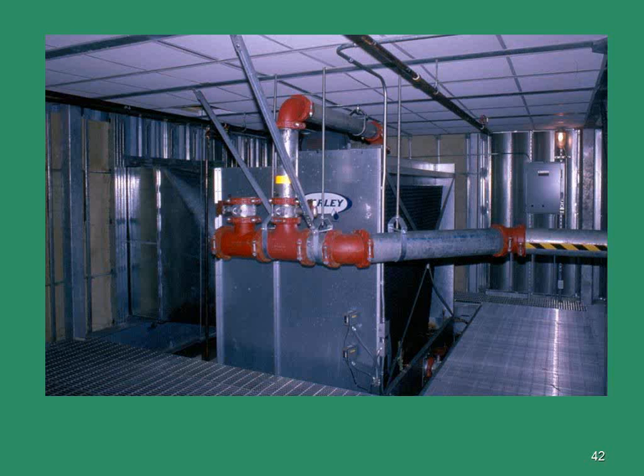Question: you've got a piece of equipment at 70 decibels at 5 feet away, what is it at, say, 1 meter? Great question. The rule of thumb is the sound level drops off by 5 or 6 decibels, 6 theoretically, 5 practically, every time you double the distance. So if your equipment was 70 at some distance, it drops by 5 decibels at double that distance, 5 more at double again, and so on. Distance can really be your friend. Putting something noisy really close to something noise sensitive is a recipe for minor disaster, at least, maybe major disaster.